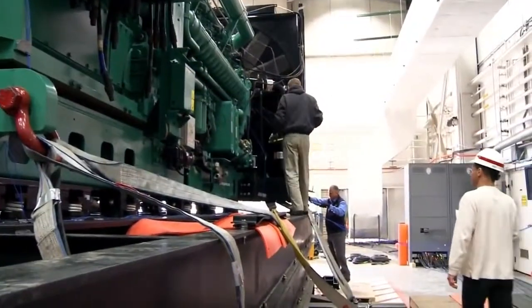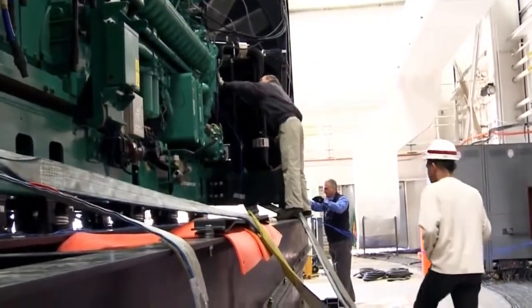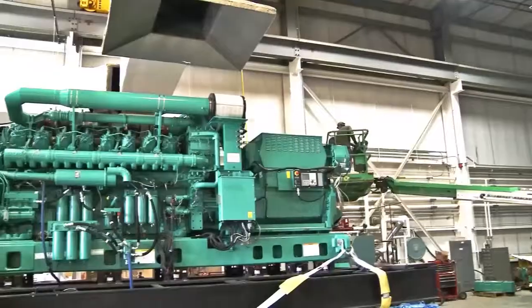The first stage of testing for seismic certification is a visual inspection of the equipment while it comes off the truck. This is followed by a pre-qualification of the unit to make sure that all the components on the unit are functioning properly the way they left the factory.